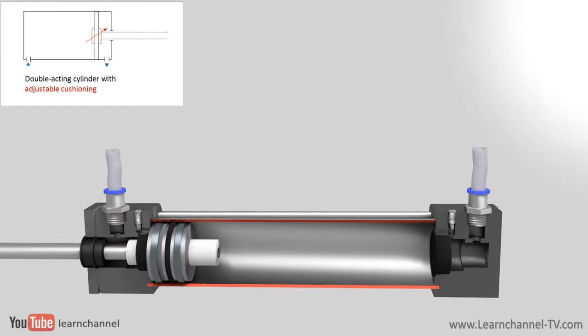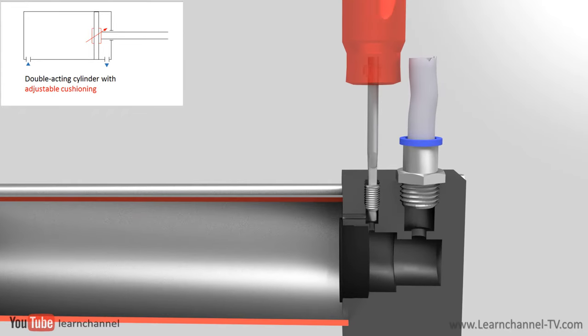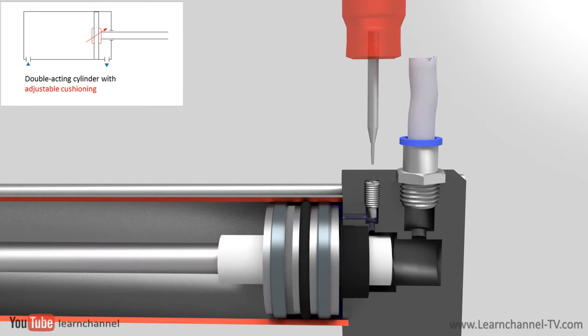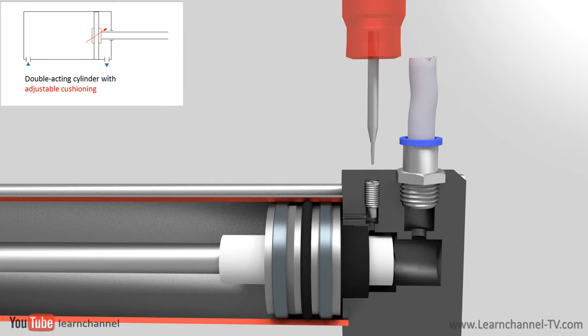By trapping a certain volume of air in the end position, a braking effect can be generated. With an adjustment screw, you can get the ideal cushioning. Too much cushioning results in slow strokes, and too little cushioning increases the end of stroke shock.